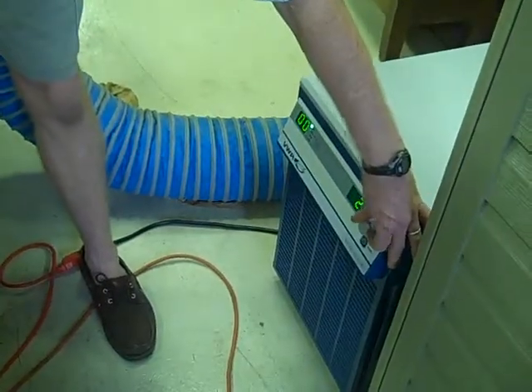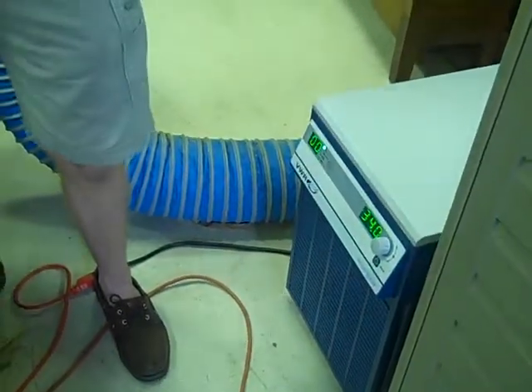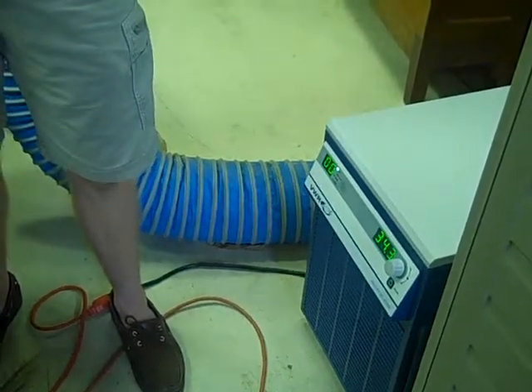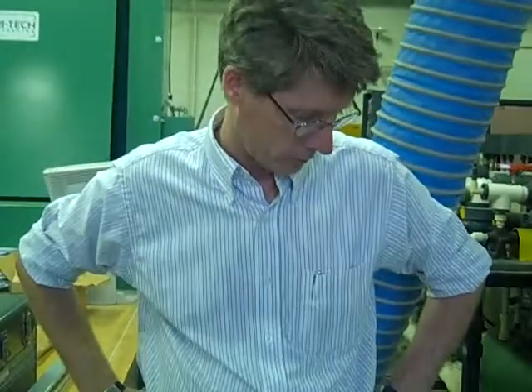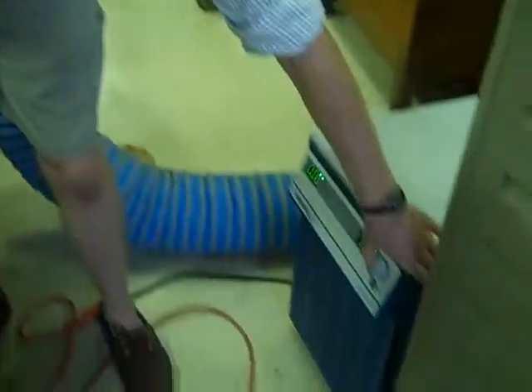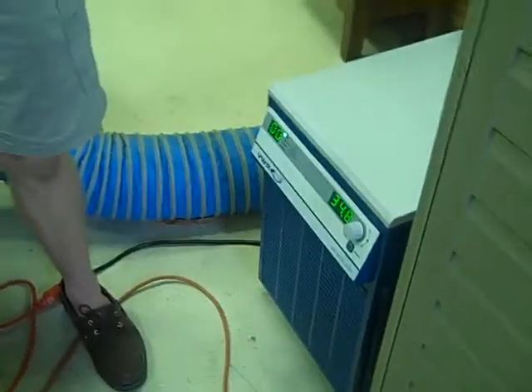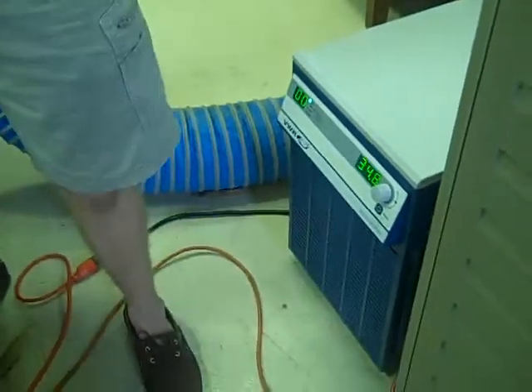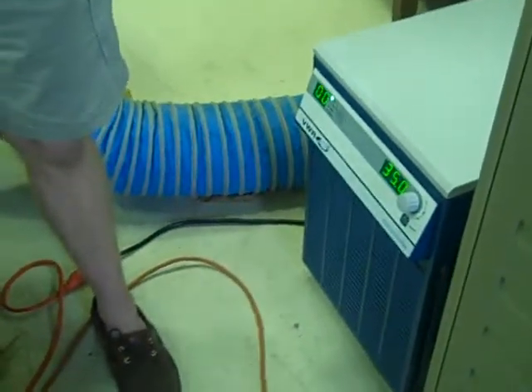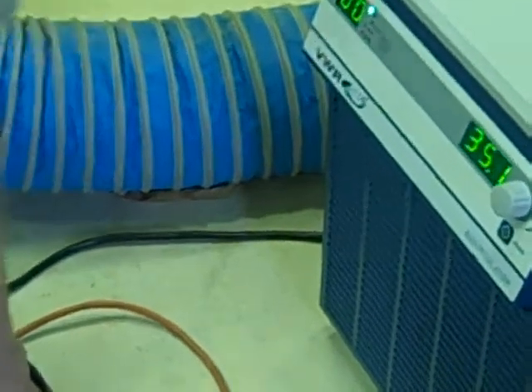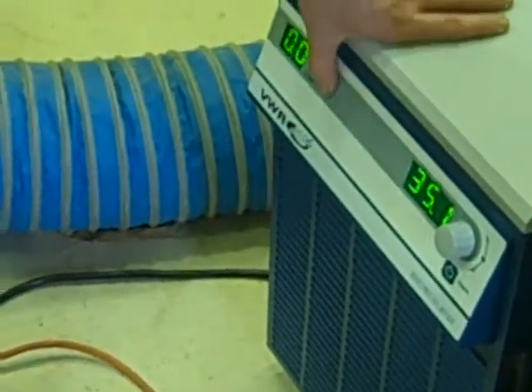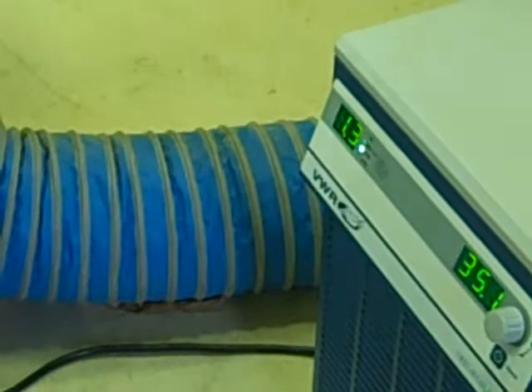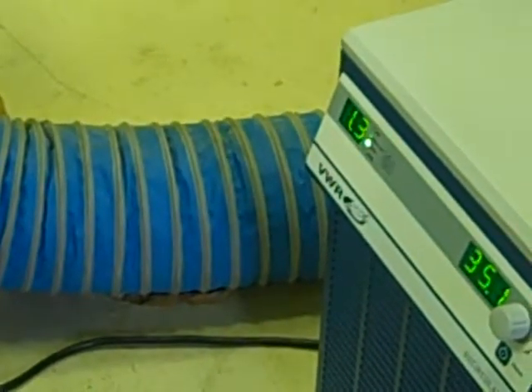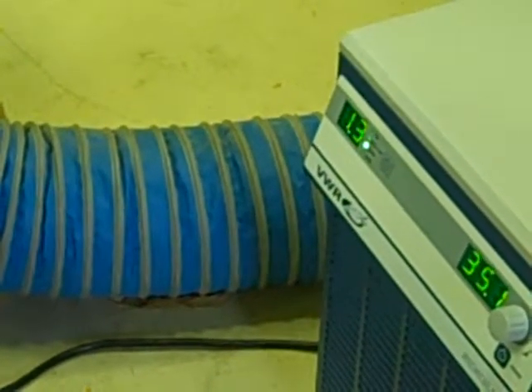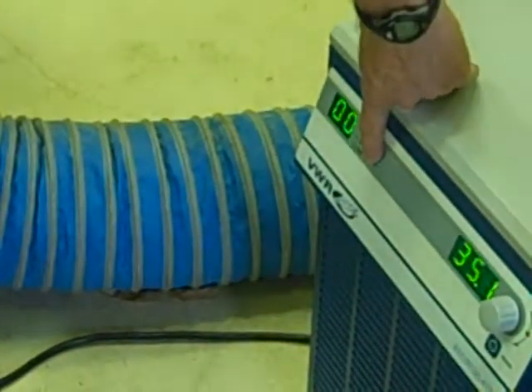Right now we're actually going to get ready to go, so we're going to set it back down to 29 degrees. That's our target. Okay. We really don't mess with the flow or anything. So if you want to see the flow, you can just scroll through it. The flow should be 1.3 gallons per minute, and you shouldn't be seeing any PSI on it for pressure.